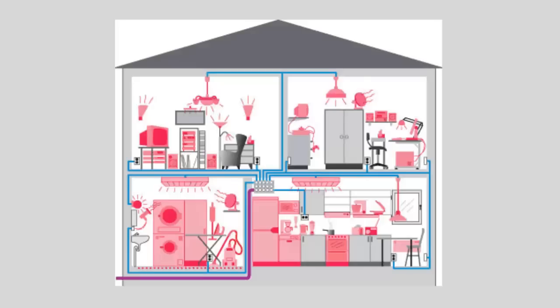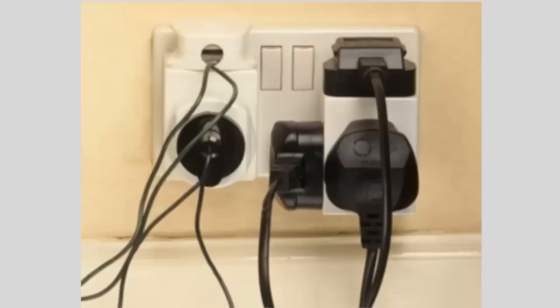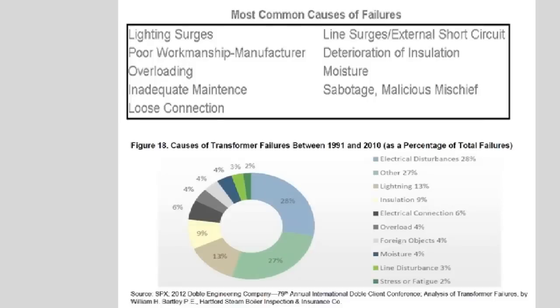Power consumption today is excessive, particularly in metropolitans. Many Tier 1, Tier 2 cities of India suffer from failure of around 1000 distribution transformers per month. One of the main reasons for this is transformer overloading. When the power drawn from the transformer exceeds the limit, it starts to wear out and its average life reduces from 30 years to around 18 years.